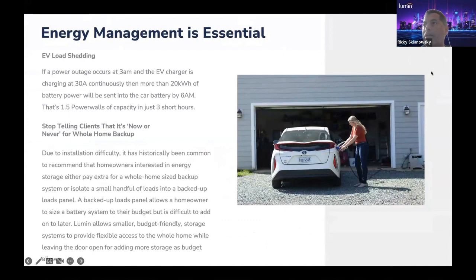Here's an example of why energy management is essential. So if a power outage occurs at 3 a.m. and the EV charger is charging at 30 amps continuously, then more than 20 kilowatt hours of battery power will be sent into the car battery by 6 a.m. That's 1.5 power walls of capacity in just 3 short hours. So in this scenario, Lumin Smart Energy Control can prevent your EV from wiping out the capacity in your battery bank, which would otherwise leave the homeowner with a drained battery in the morning.